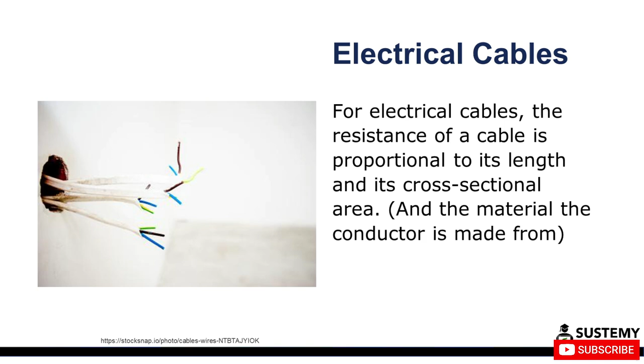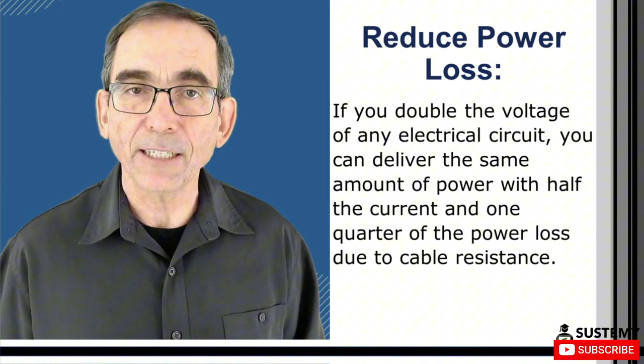For electrical cables, the resistance of a cable is proportional to its length and inversely proportional to its cross-sectional area. If I double the voltage of any electrical circuit, I can deliver the same amount of power with half the current and 1/4 of the power loss due to cable resistance. I would have to increase cable cross-sectional area 4 times, or double the cable diameter, to reduce the power losses due to cable resistance if the voltage wasn't doubled.